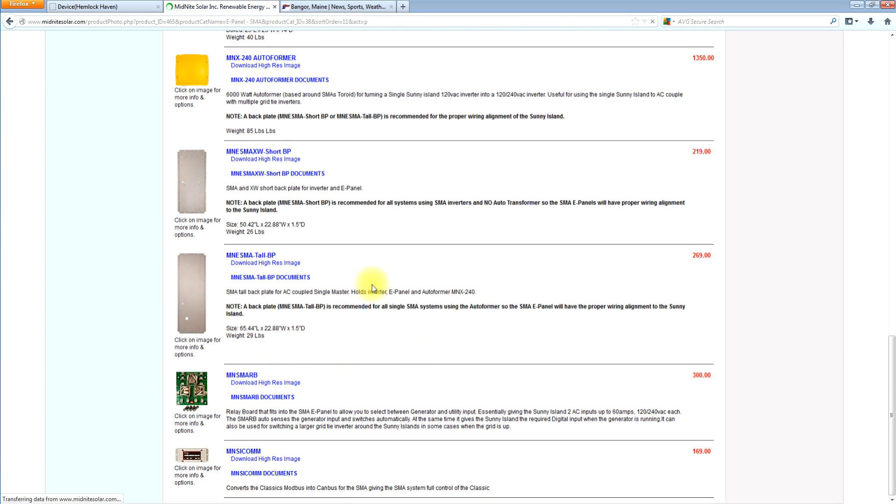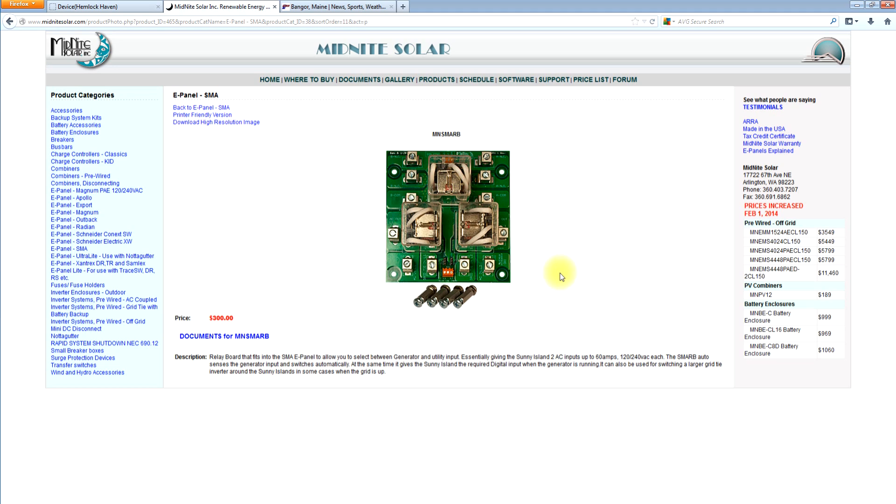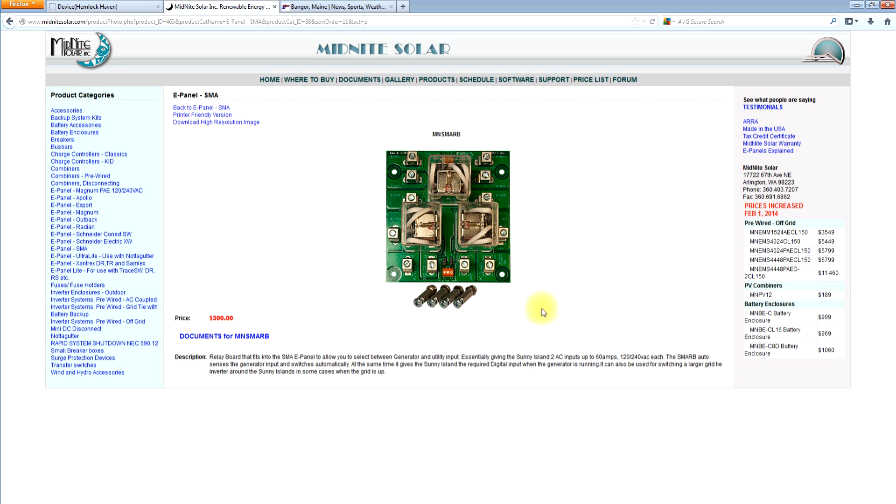This is a unique product for the Sunny Island. It's what we call the SMARB, SMA Relay Board. And we use this for a couple purposes. One is it can be used for a generator transfer. So that if you're doing a grid tie system with battery backup and you want to have two inputs, you want to have a generator and the utility grid, this can be installed in one of the e-panels. And it can actually automatically switch between the generator and the grid depending on the condition of the grid.